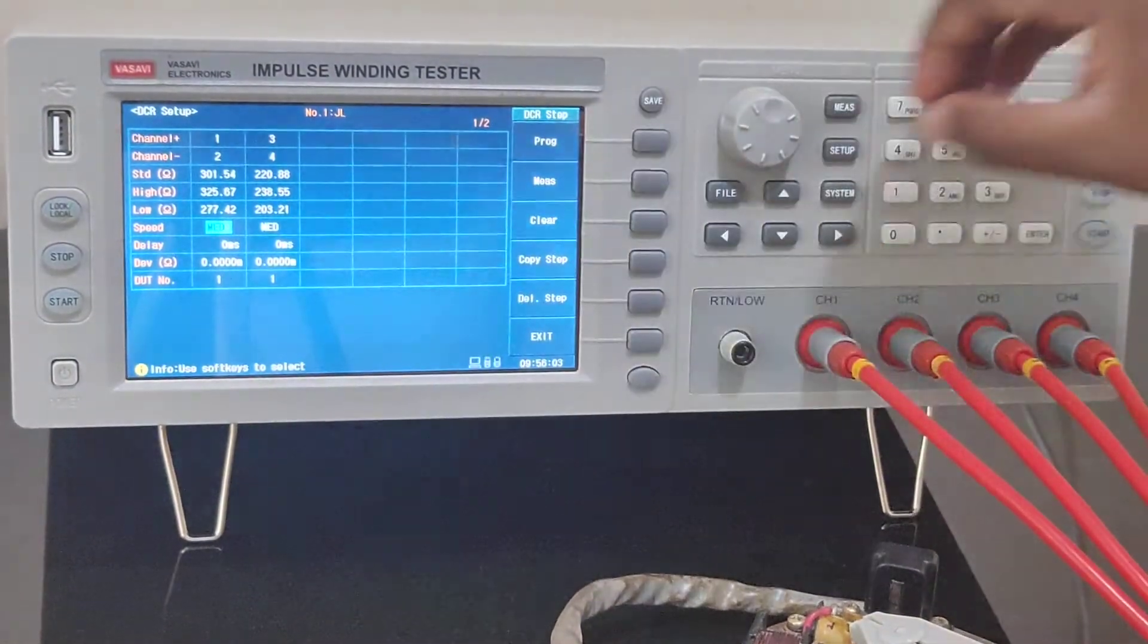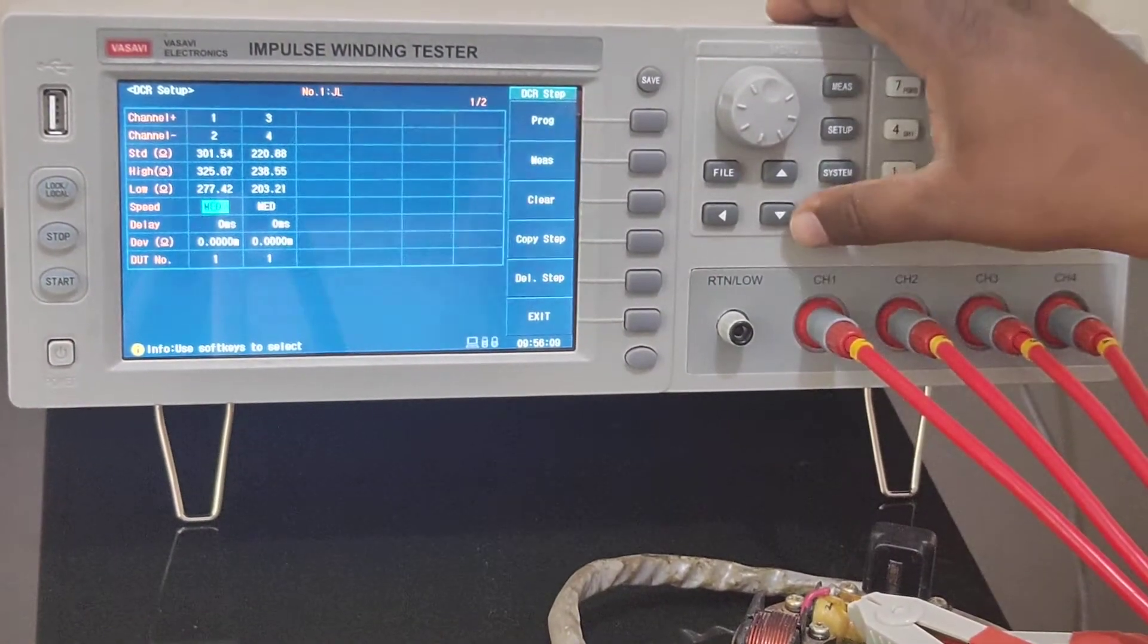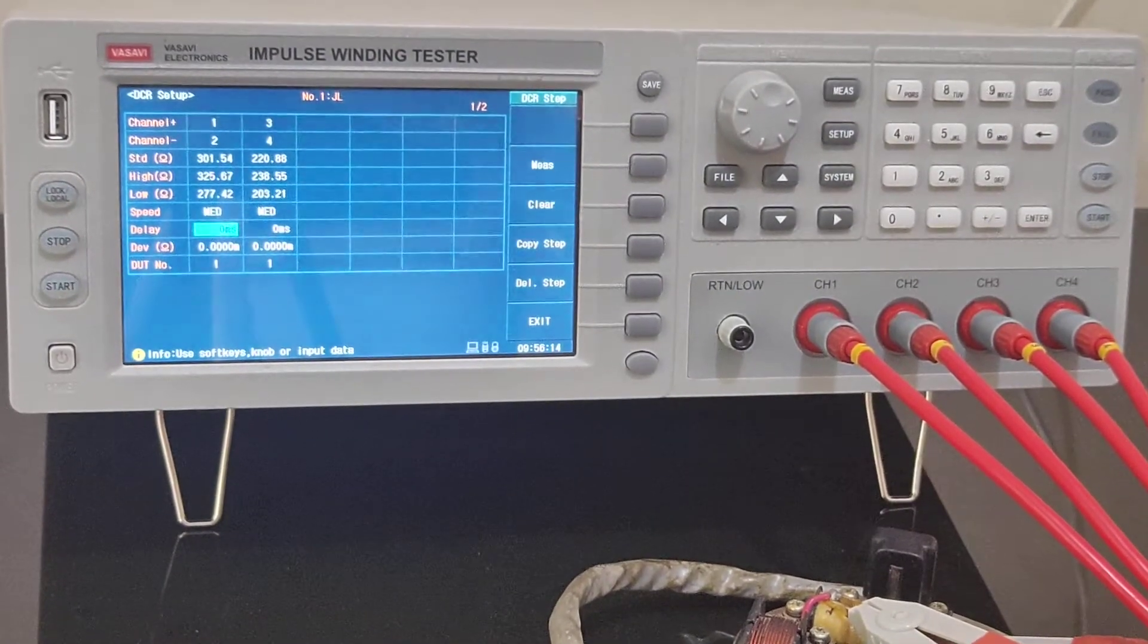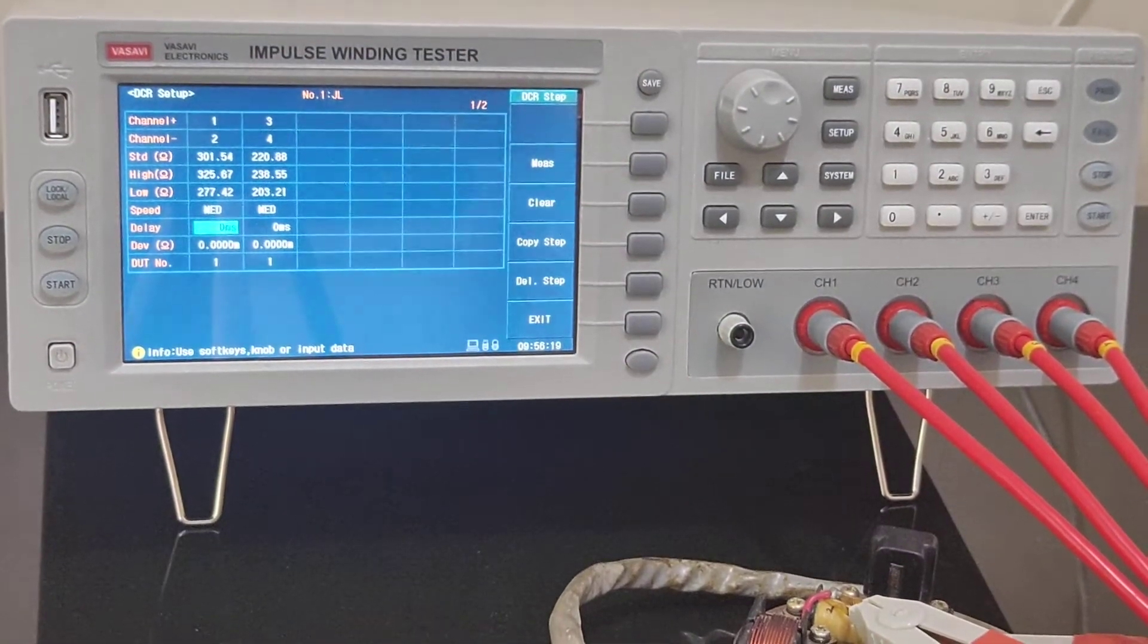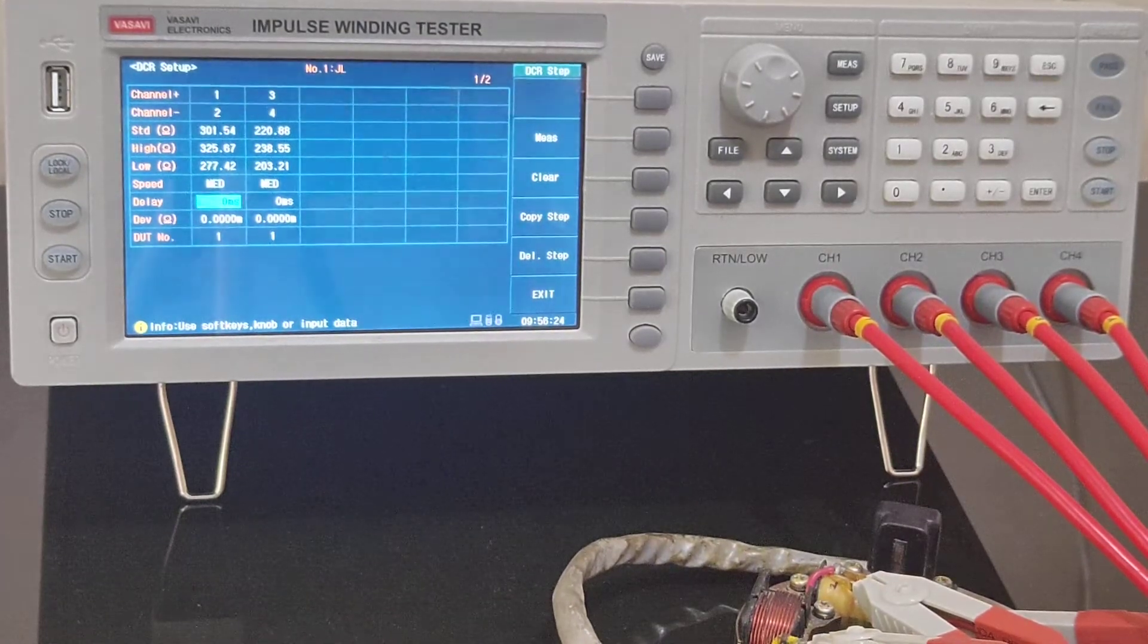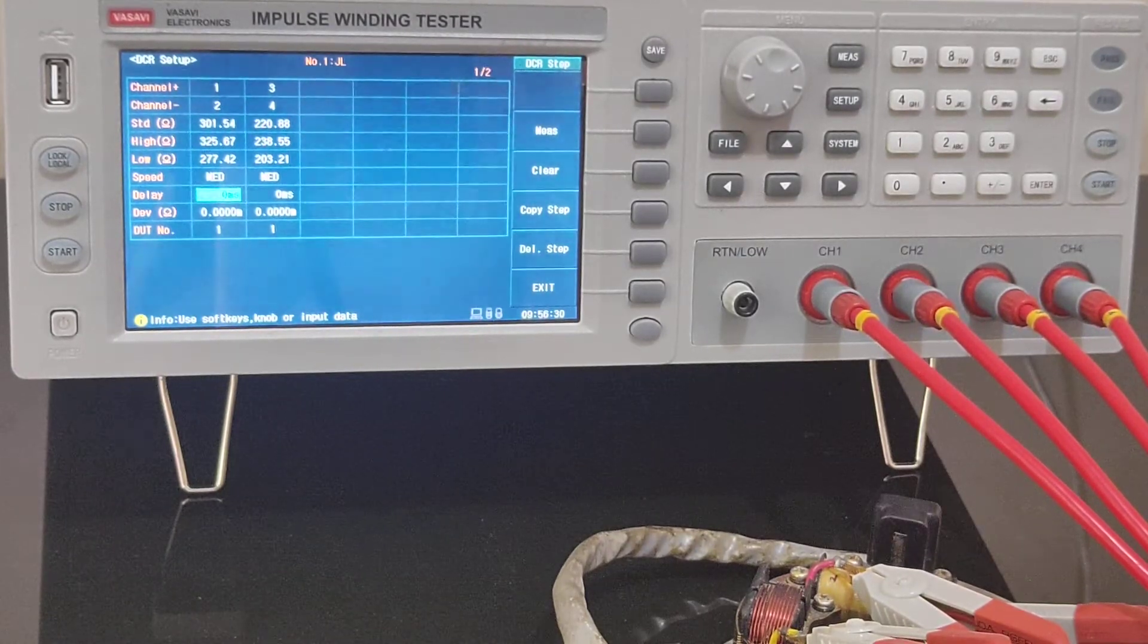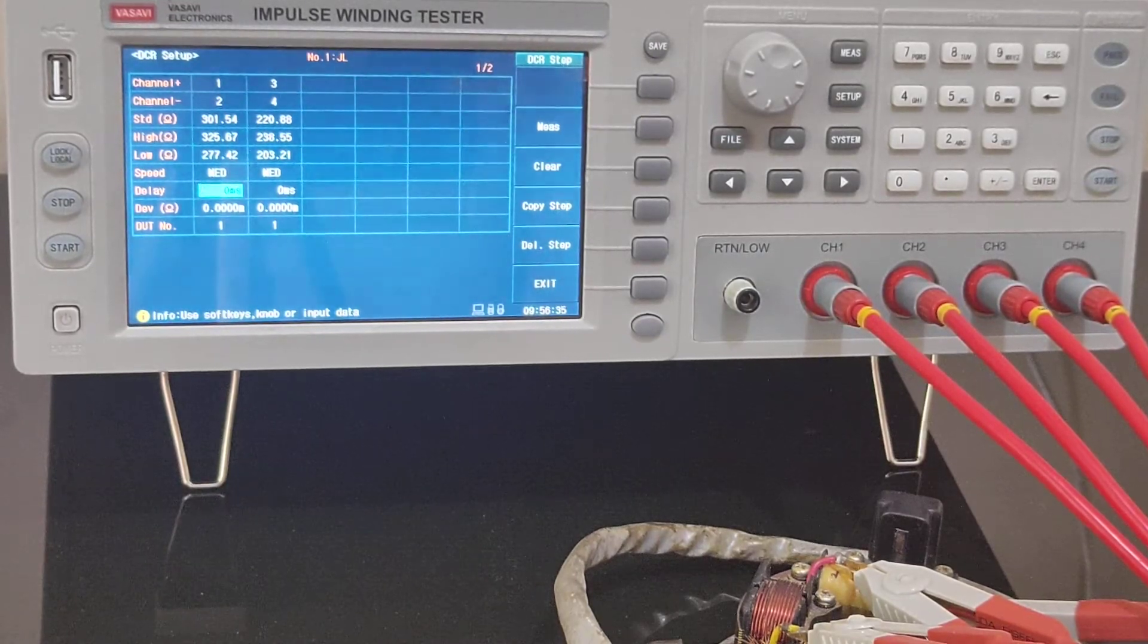In the same way if you go down you have modes - medium mode, fast mode, slow mode. In case if you wanted to give delay for measuring DC resistance you can set time here. Usually what happens is there will be high inductance coils where DC resistance may require some time, so for those particular coils you can give a time limit where it will wait for some time and test that.